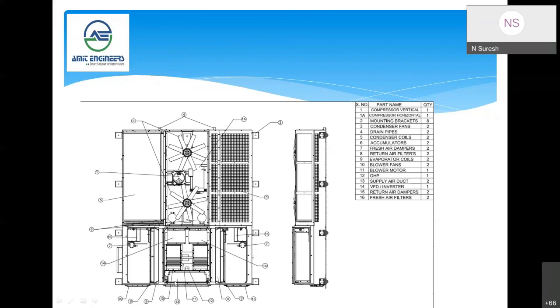Point number 12 is the OHP, the overheat protector. This is most important here in the passenger coach as well as in the system. There are electric resistance heaters, and there are 3 levels of protection in the system only for the heaters. The first level is 65 degrees Celsius, and the second is 85 degrees Celsius. And there is a fusible bulb that will blow off and switch off the system if the temperature reaches 130 degrees Celsius. Inside the system itself, from the blower, there is a small supply air duct arrangement. The air comes to this area and then passes into the duct.